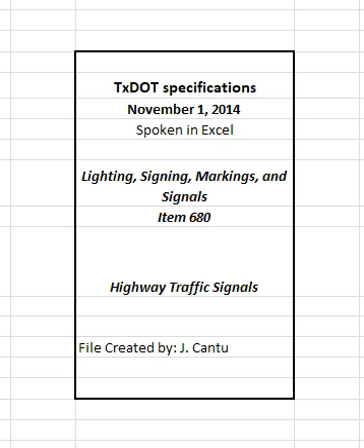3.1.1.2 Conduit. Install conduit and fittings of the sizes and types shown on the plans. Conduit of larger diameter size than that shown on the plans may be used with no additional compensation, providing the same diameter size is used for the entire length of the conduit run. Extend conduit in concrete foundations 2 to 3 inches above the concrete. Seal the ends of each conduit with silicone caulking, or other approved sealant, after all cables and conductors are installed.